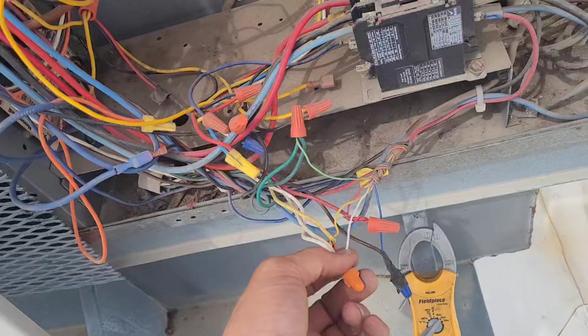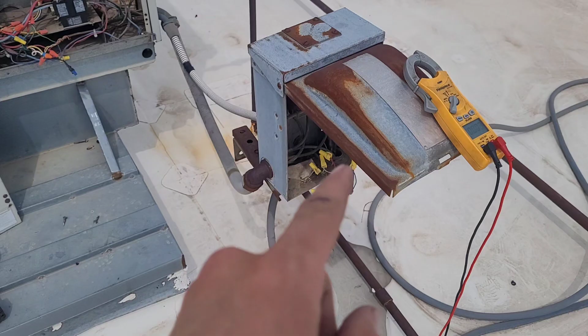So that makes two systems that have burnt wires, but why are they tied together? Are they both controlled by the same thermostat? If so, that's really weird, and I don't know how it would even work without a relay separating the two transformers. Very strange. So same symptoms in this one. We have power here and here. I just shut off the power there. Let's go see if the contactor is still pulled in. Oh, I can hear it from here. It is still pulled in.